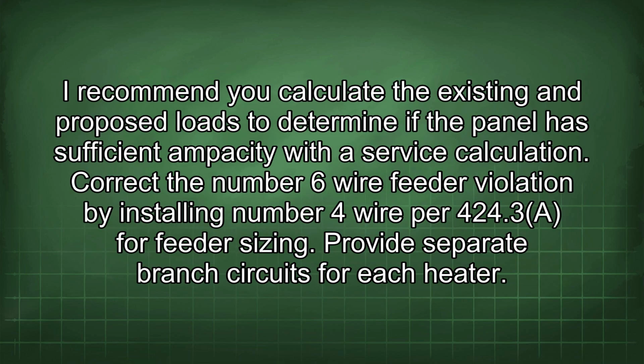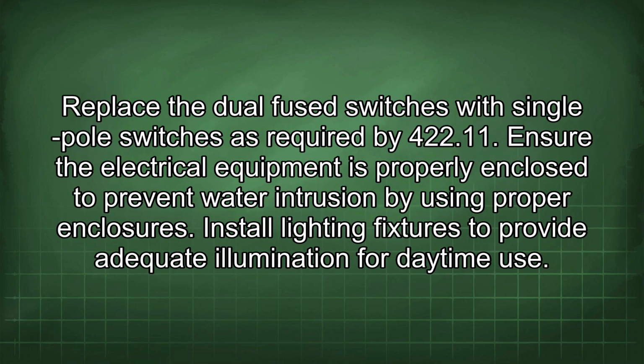I recommend you calculate the existing and proposed loads to determine if the panel has sufficient ampacity with a service calculation. Correct the number 6 wire feeder violation by installing number 4 wire per 424.3 for feeder sizing. Provide separate branch circuits for each heater. Replace the dual fuse switches with single pole switches as required by 422.11. Ensure the electrical equipment is properly enclosed to prevent water intrusion by using proper enclosures.